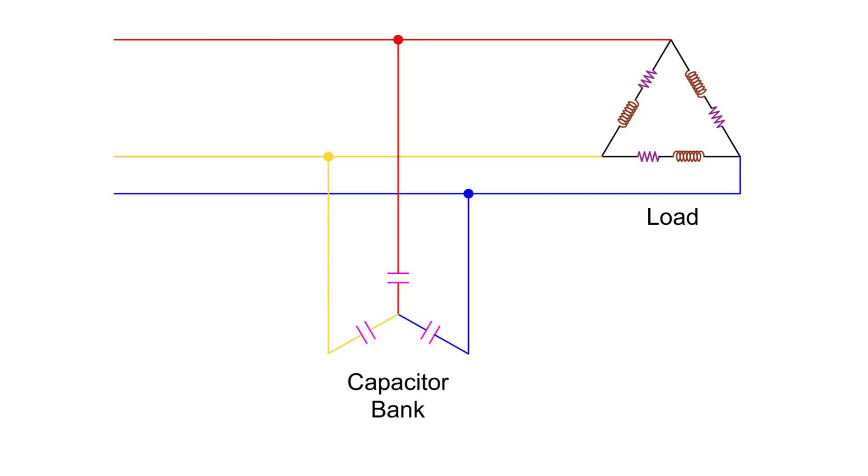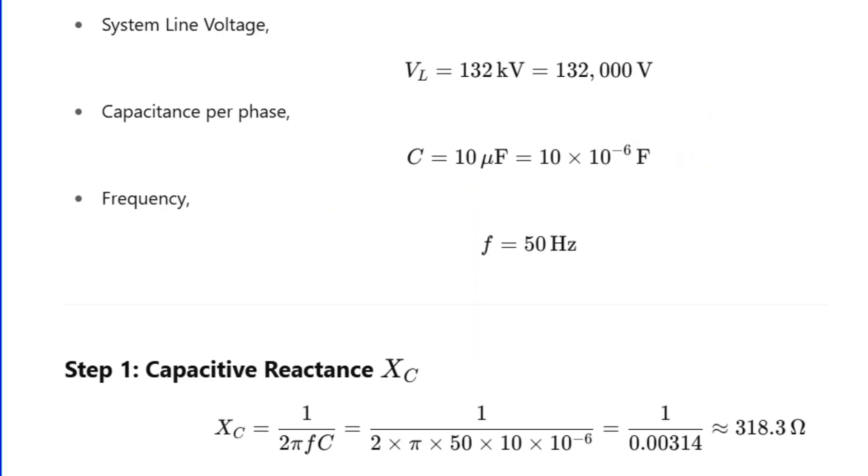Let's take a simple numerical example to see this more clearly. Suppose we have a three-phase 132 kilovolt system, and let's assume we use capacitors of 10 microfarads in each phase. First, let's calculate the capacitive reactance: XC equals 1 divided by 2πfC, where f is the system frequency, which is 50 hertz.